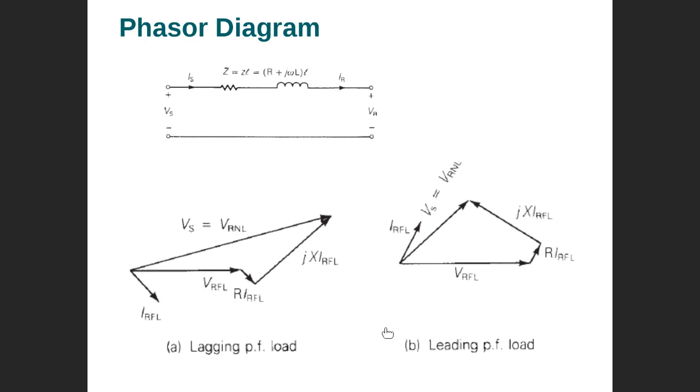is operating. It's allowed. If the factory or the company has a low power factor and exceeds the limit of, for example, 0.87, if they exceed, they pay a penalty to Kahramaa. They pay money because their power factor is low. So every factory and industry needs to correct their power factor on their own. They install capacitors to improve the power factor in their company, because they measure the power factor and then they will pay a penalty.